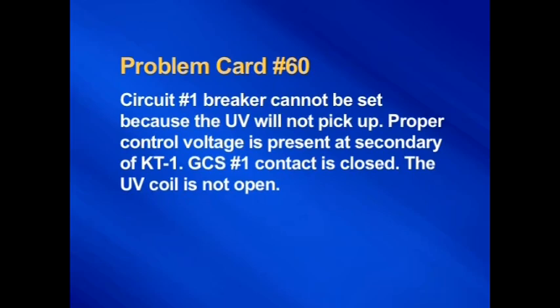Problem card number 60. Circuit number 1 breaker cannot be set because the UV will not pick up. Proper control voltage is present at the secondary of KT1. GCS number 1 contact is closed. The UV coil is not open. Circuit number 1 breaker can't be set.